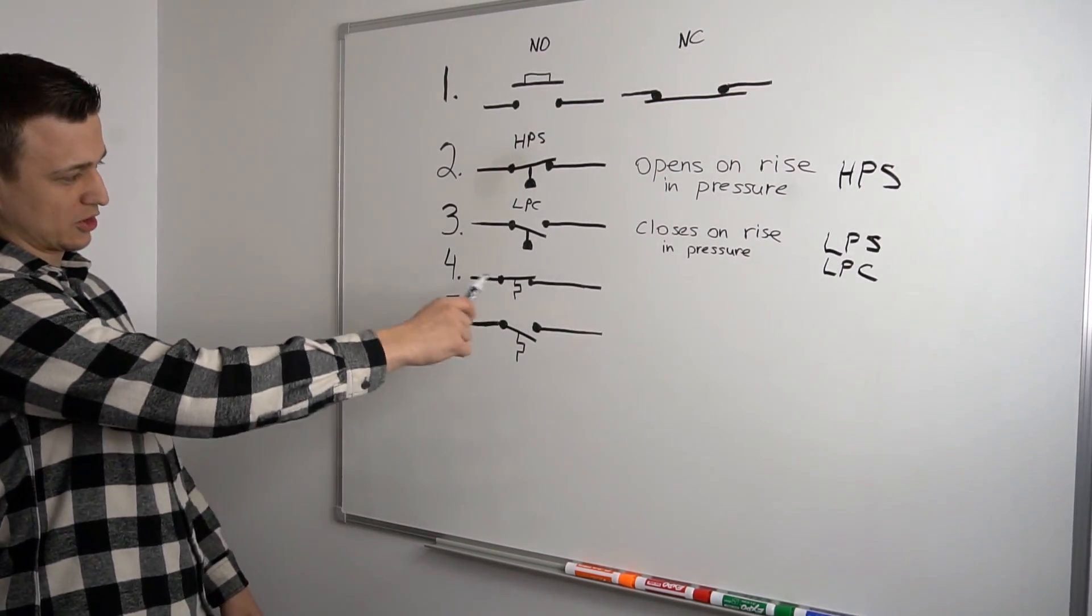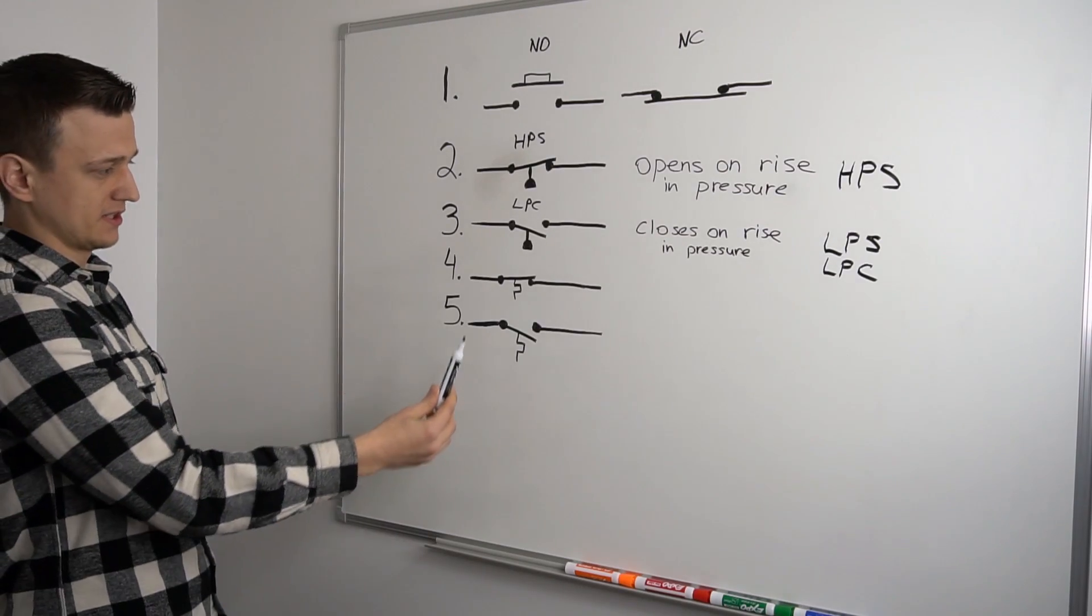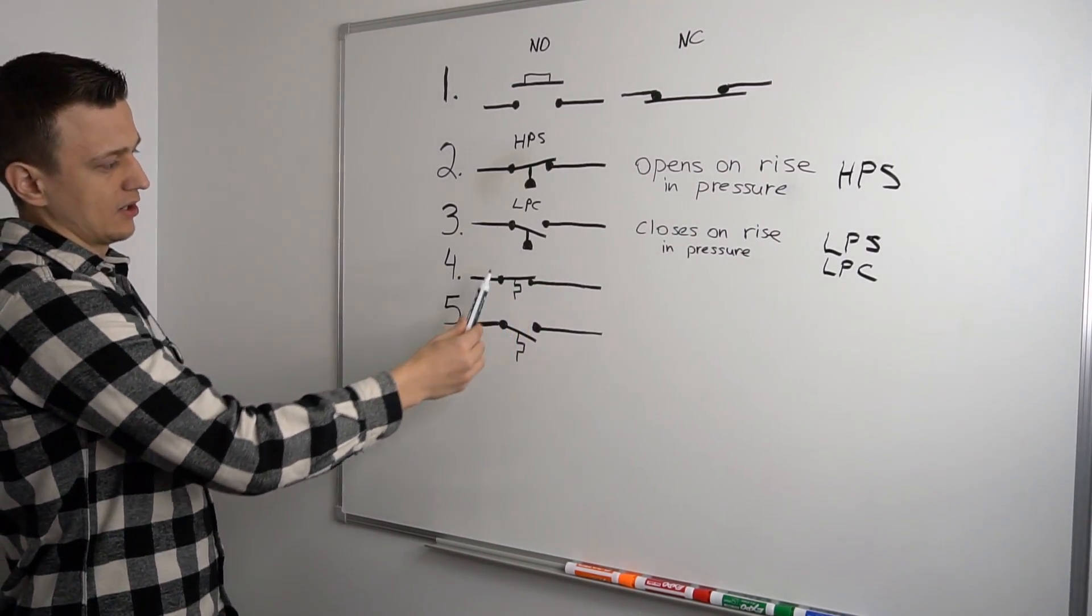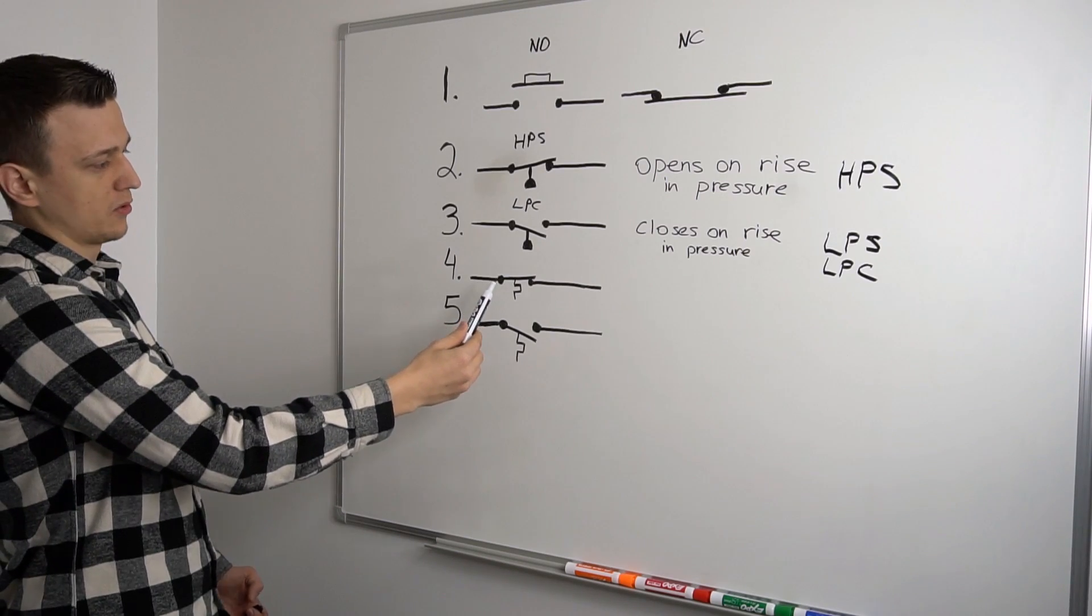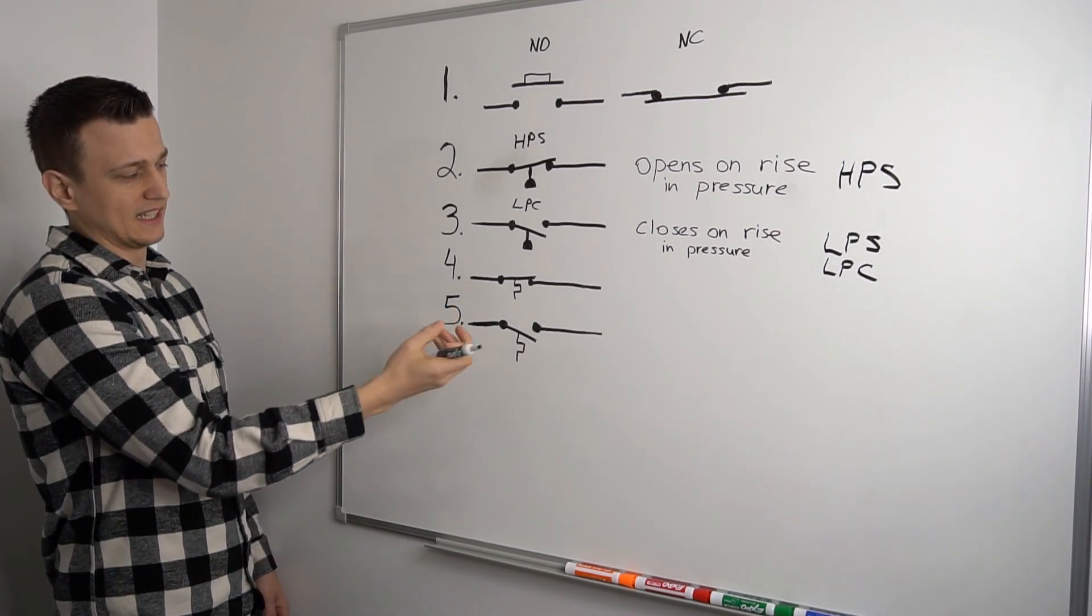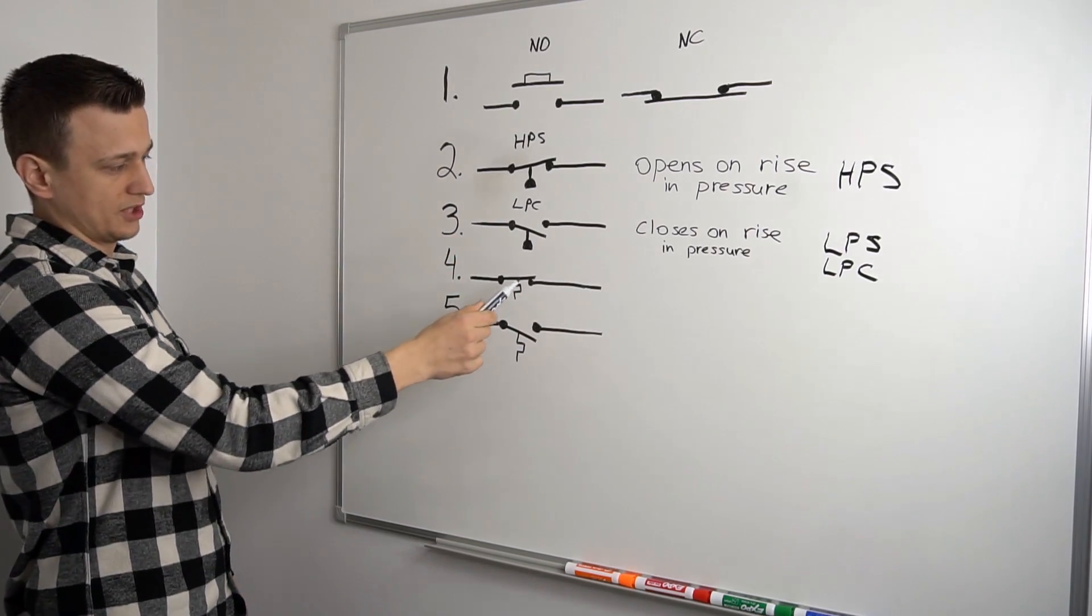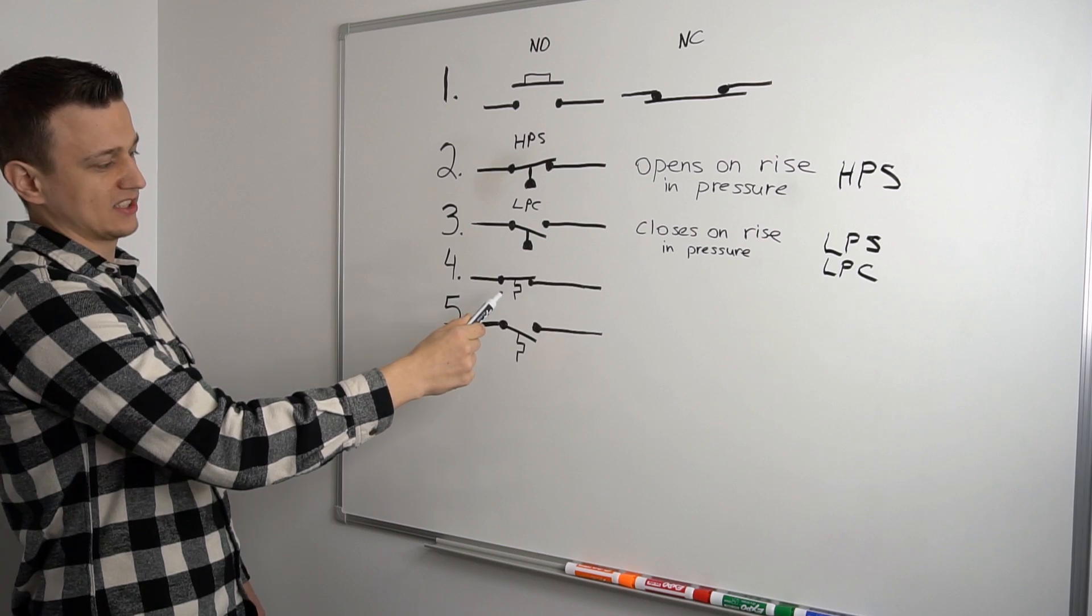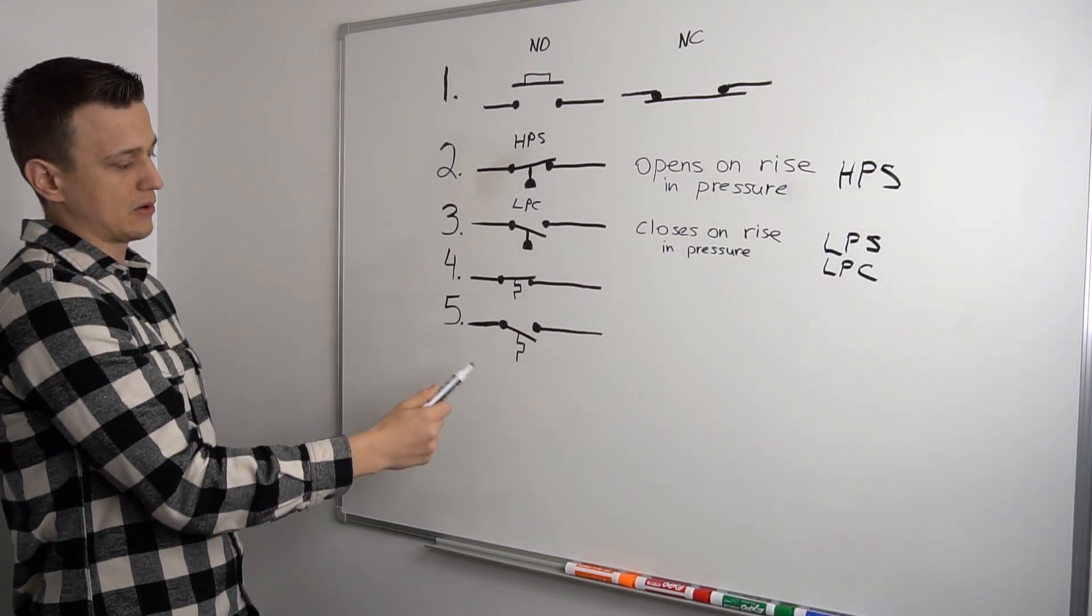And moving on to our next two switches, we have thermostat switches or basically heat switches. This one right here opens if the temperature gets hotter. So there's a sensor or usually it's a bimetal or a snap disk. If that thing heats up enough, it'll open up and interrupt the circuit.